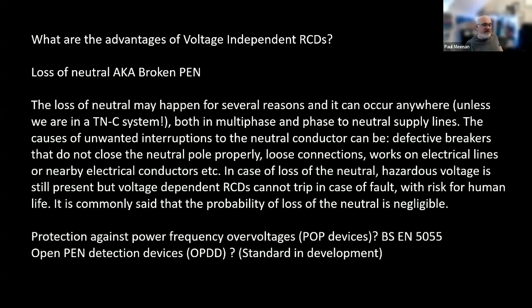The loss of neutral may happen for several reasons, and anywhere, unless we're in a TN-C, which we don't recommend. Both in multi-phase and phase to neutral supply lines, the cases of unwanted interruptions to the neutral conductor can be defective breakers that do not close the neutral, loose connections, works on electrical lines or nearby electrical conductors. In the case of a loss of neutral, hazardous voltage is still present, but the voltage dependent RCDs cannot trip in case of this fault, with risk for human life. It is commonly said that probability of loss of the neutral is negligible, but as you can see, it is growing. So we need to just be mindful of it.